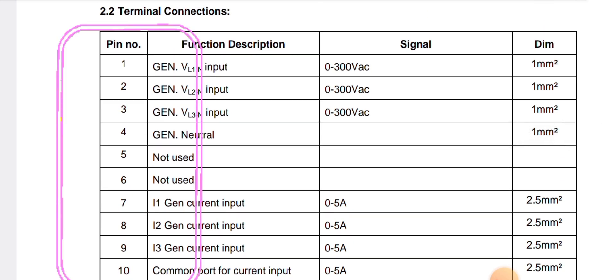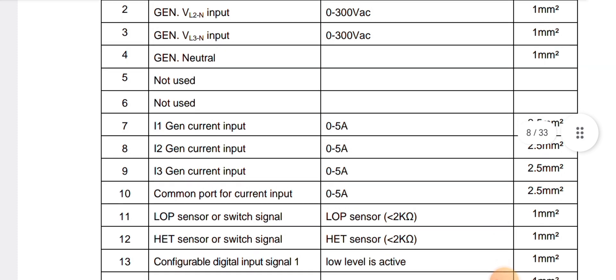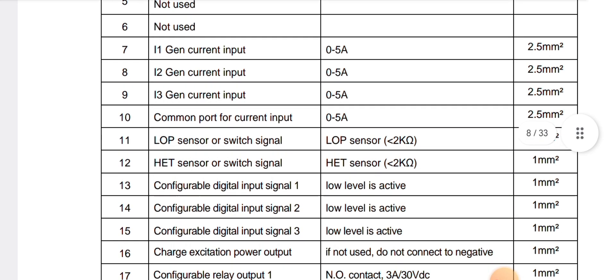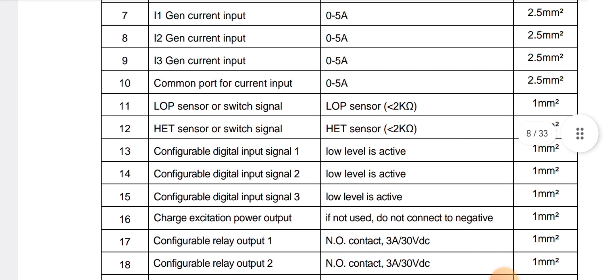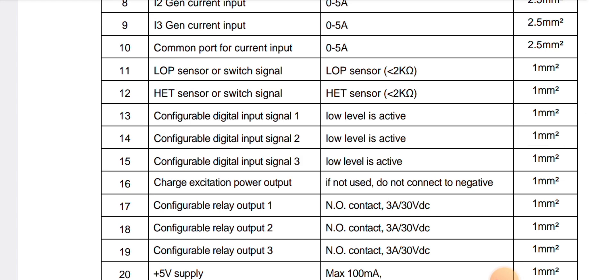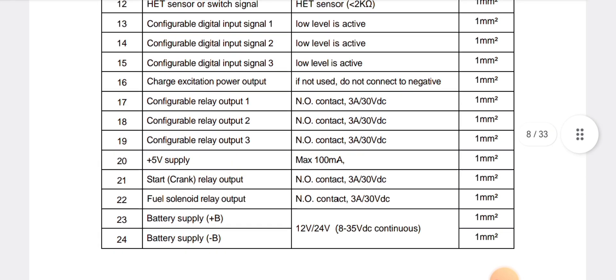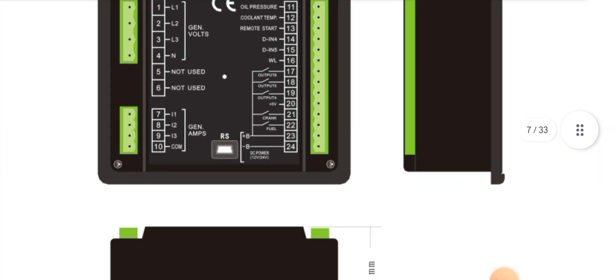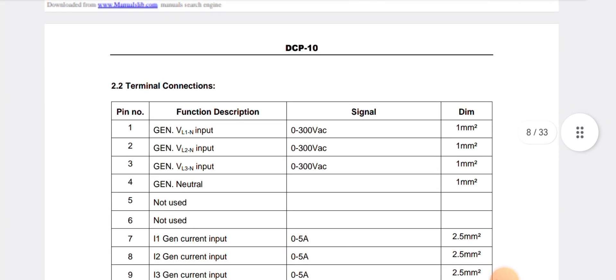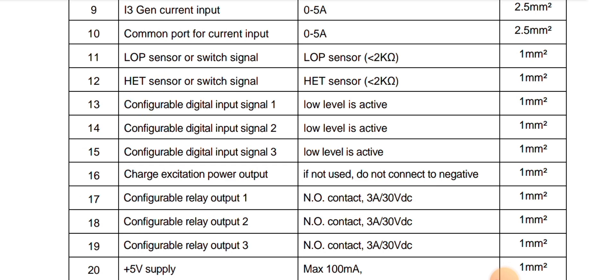As you can see, for the three-phase gen voltage, the signal is maximum 300V AC — gen V1 neutral input, three phases and one neutral. Pins 5 and 6 are not used. Pins 7, 8, 9, and 10 are for the CT. Pin 11 is low pressure, pin 12 is high engine temperature, and pin 13 is a configurable digital input. You can configure this through the software for your specific requirements. Pin 14 low level is active, and pin 15 is configurable digital input signal 3 and signal 2.